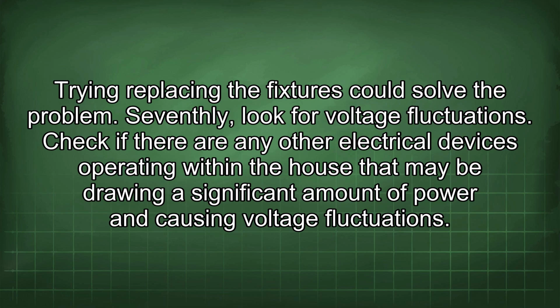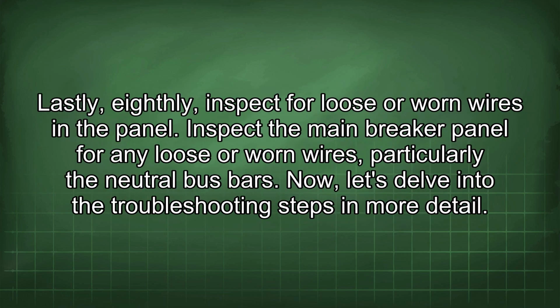Seventhly, look for voltage fluctuations. Check if there are any other electrical devices operating within the house that may be drawing a significant amount of power and causing voltage fluctuations. Lastly, eighthly, inspect for loose or worn wires in the panel. Inspect the main breaker panel for any loose or worn wires, particularly the neutral bus bars. Now let's delve into the troubleshooting steps in more detail.